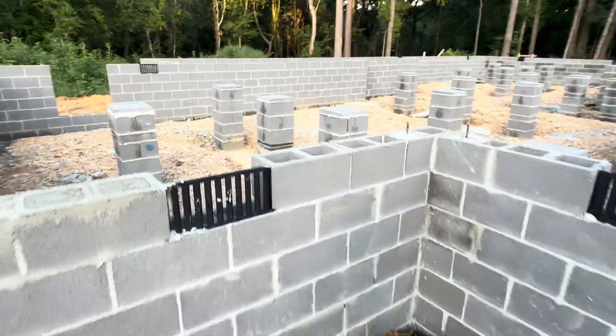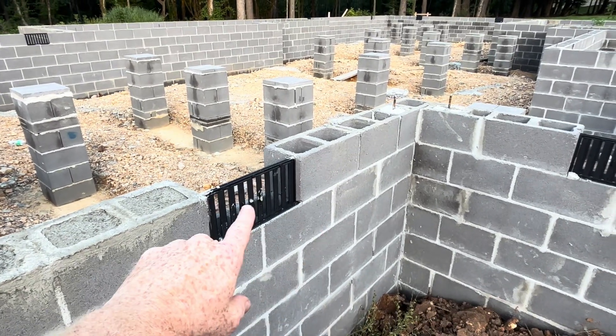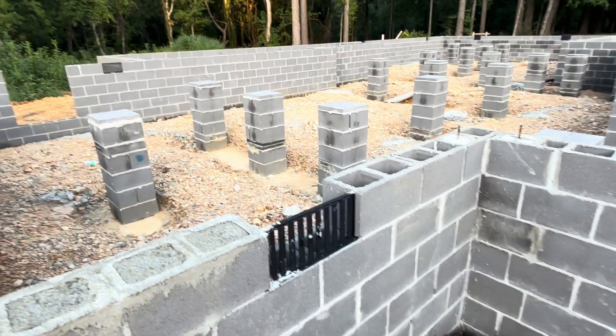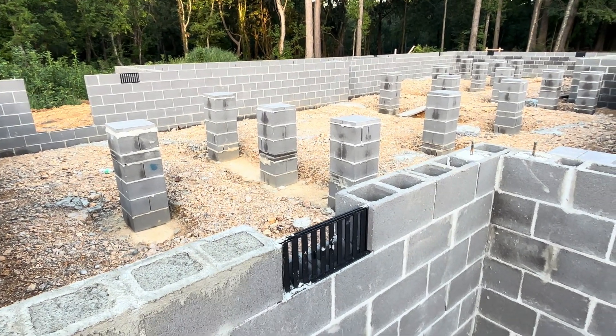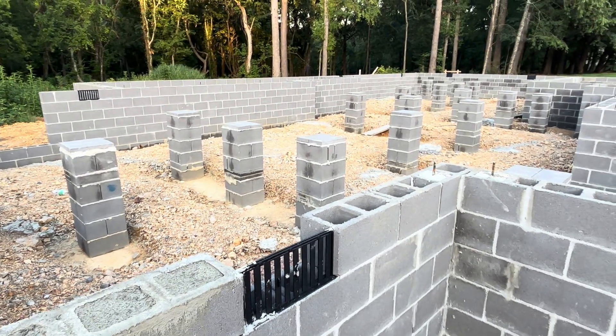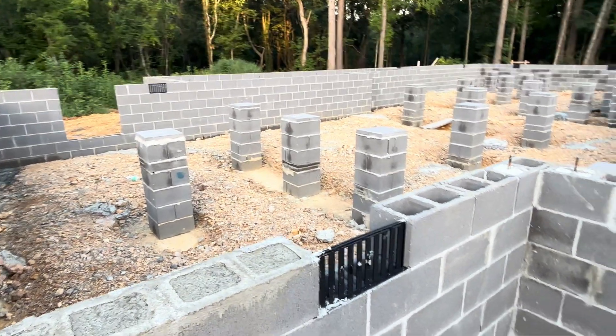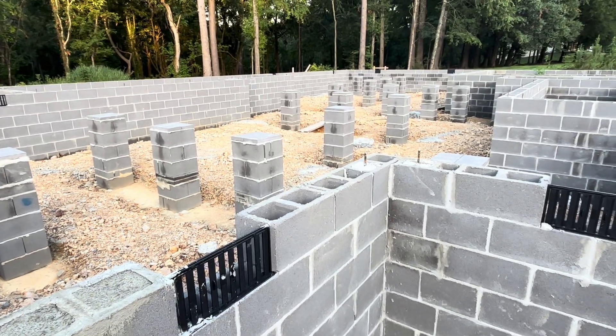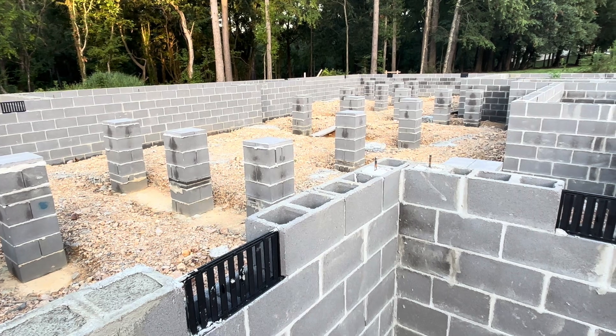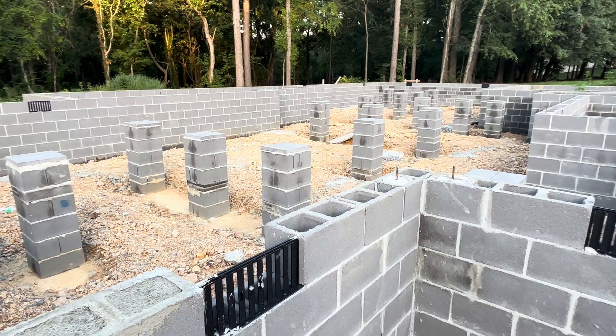The problem here — like I said, we're in northwest Georgia where it's humid. Hot, humid air in the summer goes through the open vent into a much cooler crawl space where it condenses, so it's essentially raining in a crawl space. Most people put fiberglass insulation in a crawl space, and that fiberglass insulation will collect all the condensated water from the atmosphere and weigh down the insulation, which becomes useless if it's not in 100% contact with the surface it's trying to insulate.